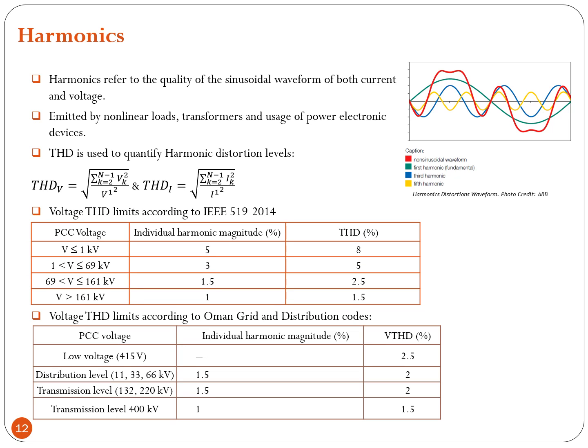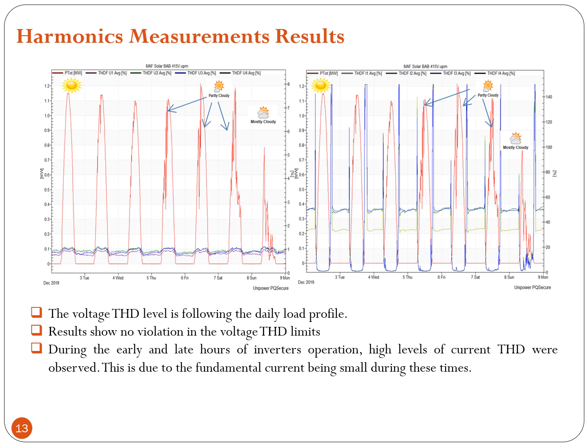Harmonic levels refer to the quality of the sinusoidal waveform for both current and voltage emitted by nonlinear loads, transformers, and the usage of power electronic devices. Total harmonic distortion is used to quantify the harmonic distortion level. The 5% voltage total harmonic distortion limit is according to IEEE 519-2014, while 2% for the distribution level is the limit of total harmonic distortion according to the Oman grid and distribution code.